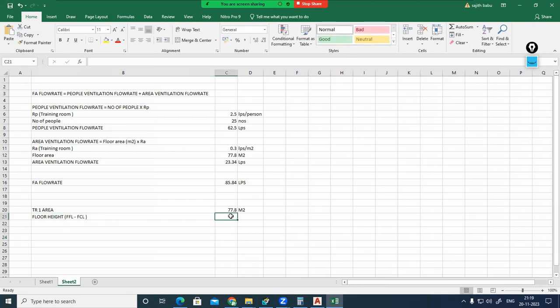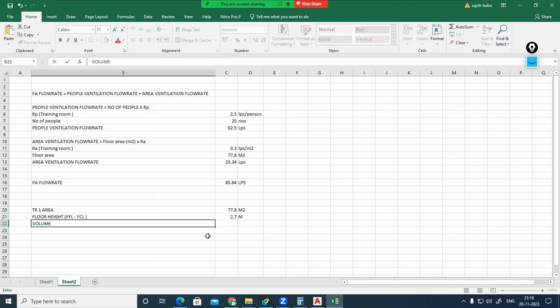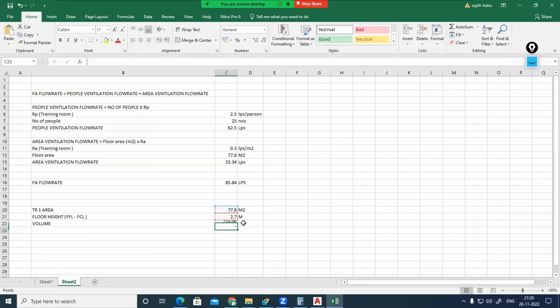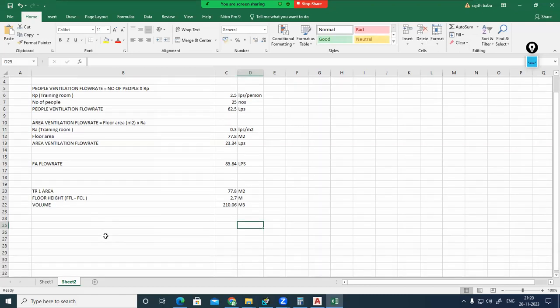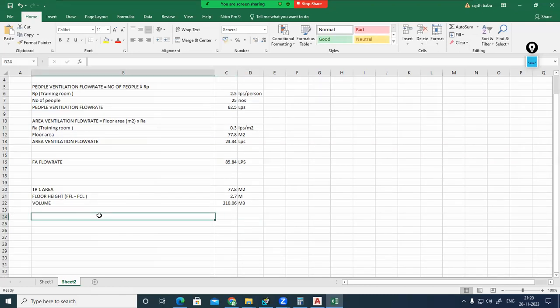Let's say here we have a 2.7 meter ceiling height. 2.7 meter. So the volume of the space will be, not meter square, it is meter cube. The volume of the space will be area into height, 77.8 into 2.7. How much? 210.06 cubic meter, meter cube. Now, your ventilation flow rate with respect to the air changes per hour.